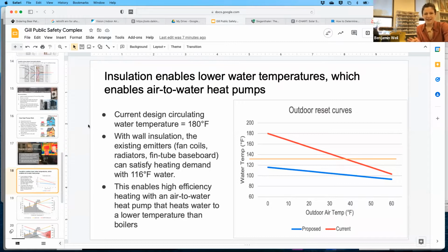Insulation enables lower water temperatures, which enables air to water heat pumps. So the current design circulating water temperature is 180 degrees Fahrenheit. And this is basically determined by the size of the heat emitters in the distribution system, and also the hourly heating demand of the space. And insulating will reduce the heat load from the space. So with the same size emitters, you can use lower temperature water and still adequately heat the space.